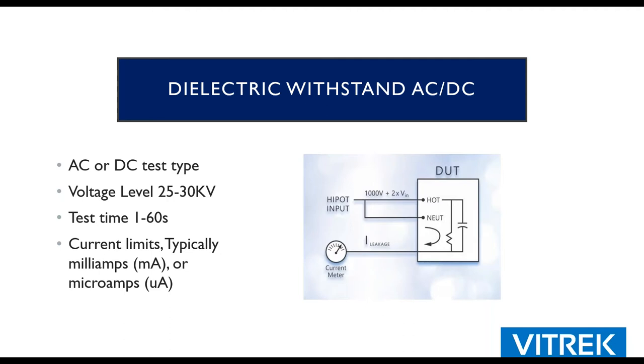The most common compliance test is the hipot test, also known as dielectric withstand in AC or DC. Voltages are typically two times line voltage plus a thousand, but can range anywhere from 25 volts up to 30,000 volts or more depending on the product's operating voltage. Test times can range from 100 milliseconds for quick component testing, typically 60 seconds is very common, and some people do long-term stress studies over 60 or 90 days or even a year. Ultimately you're measuring current between two conductors, represented in microamps or milliamps.